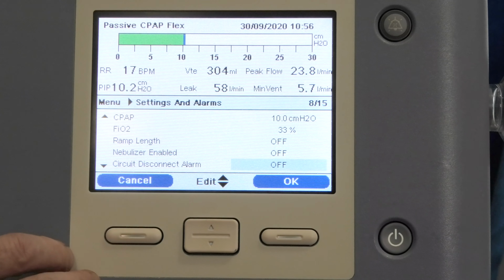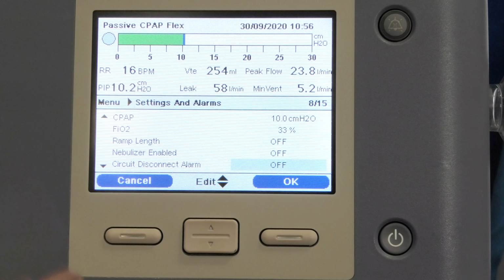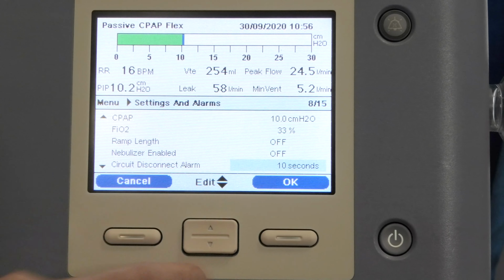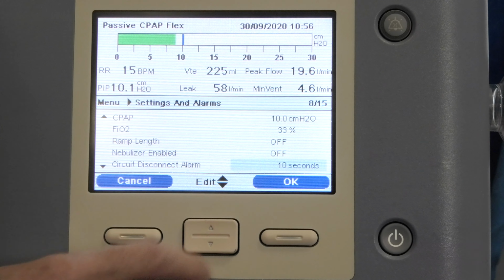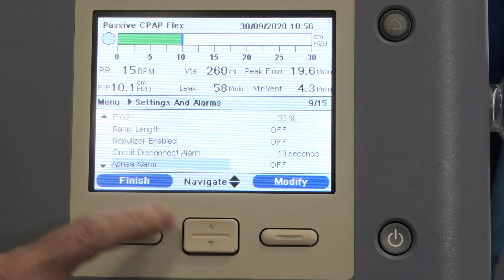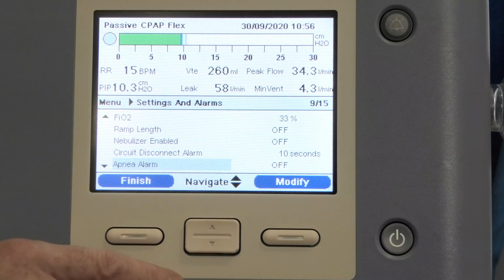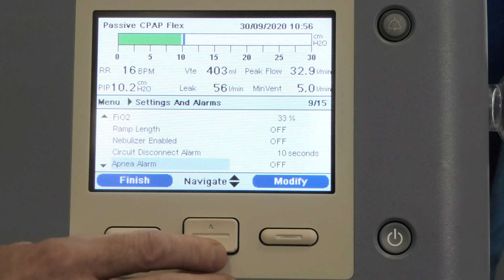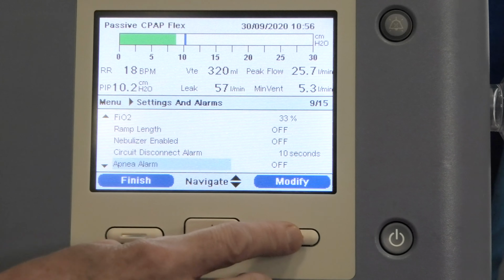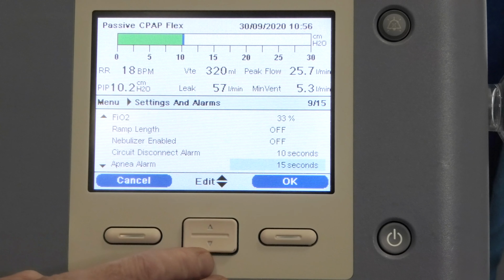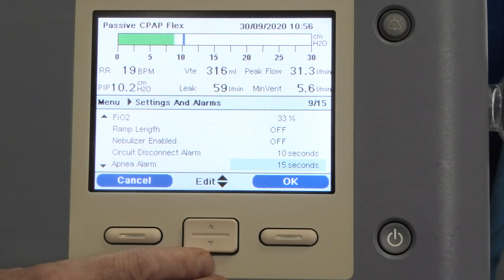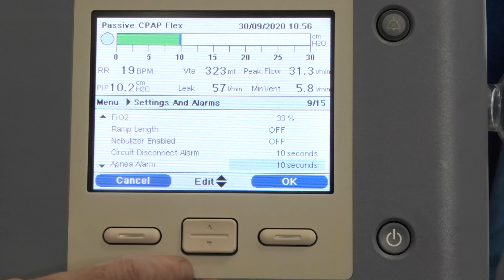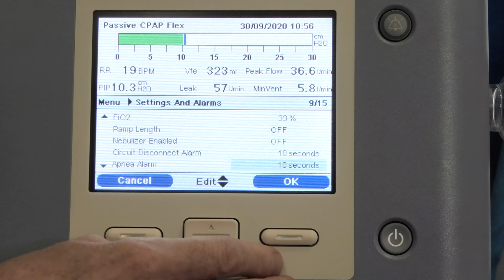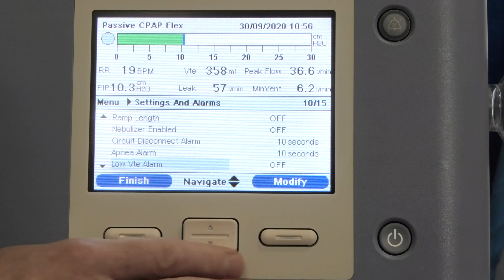I would set my circuit disconnect alarm. I want to know if the circuit's come off my patient, so I would probably set that at 5 or 10 seconds. Press OK. The same with the apnea alarm. I want to know if my patient's not taken any breaths, especially on CPAP. So again, I would modify it and I would turn on my apnea alarm to probably 10 seconds, depending on your patient's respiratory rate, and press OK.